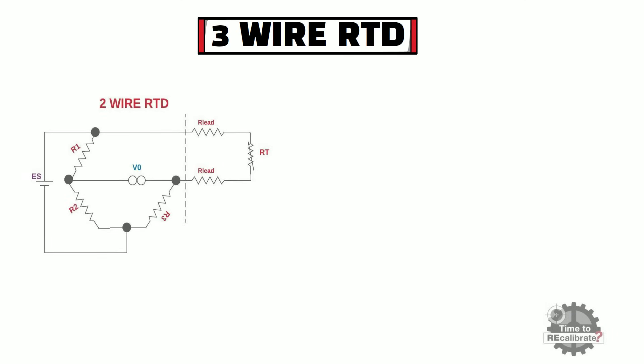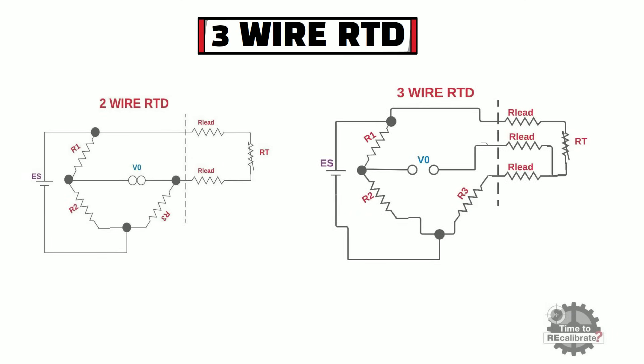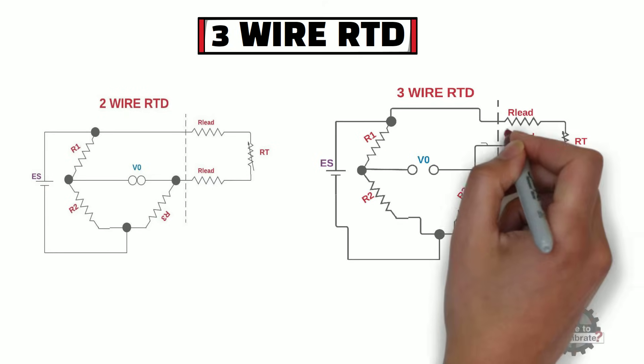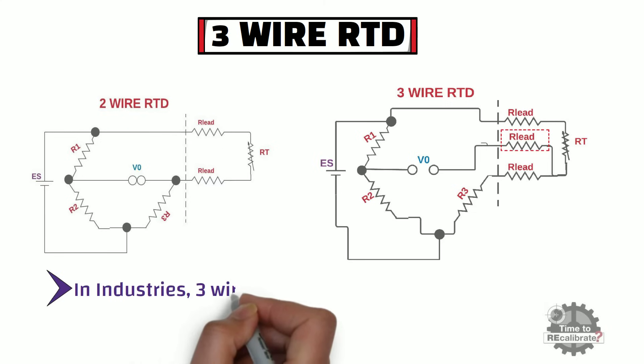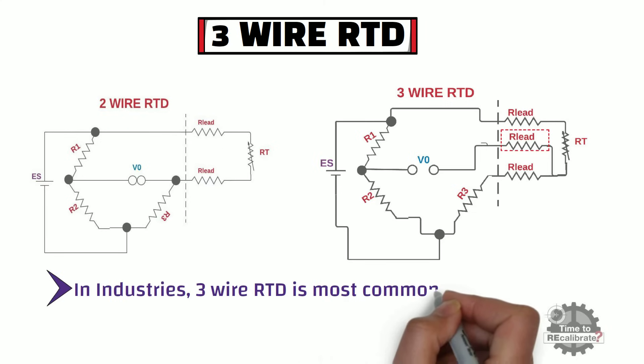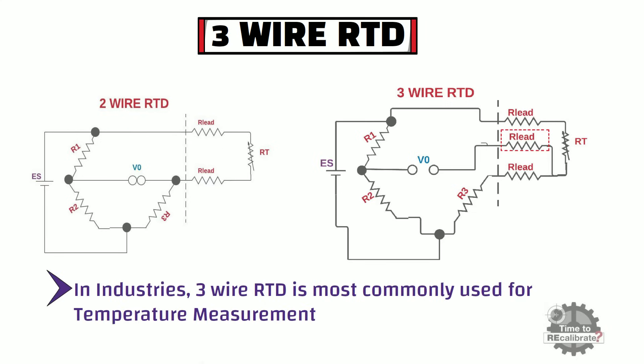As you can see from the pictures, the major difference between 2-wire RTD and 3-wire RTD is that the 3-wire RTD has an extra lead wire. This extra lead wire eliminates the effect of lead resistance in the circuit, which is not possible in 2-wire RTD. Hence, this is the reason that 3-wire RTD is the most commonly used RTD in industries.